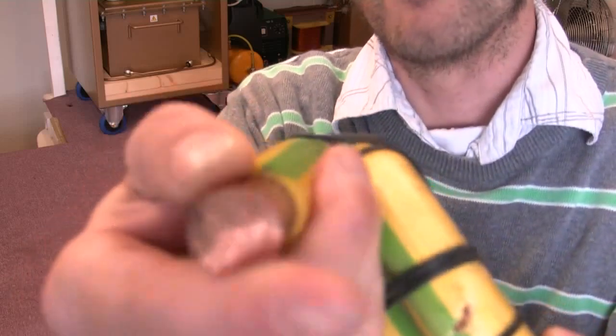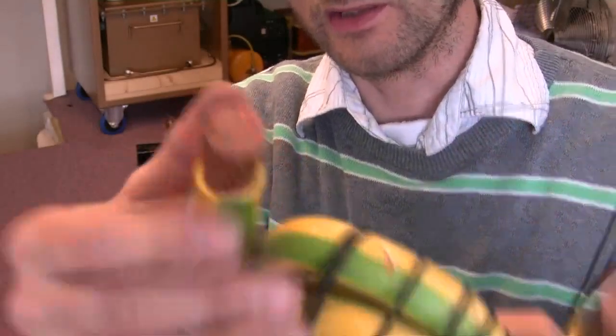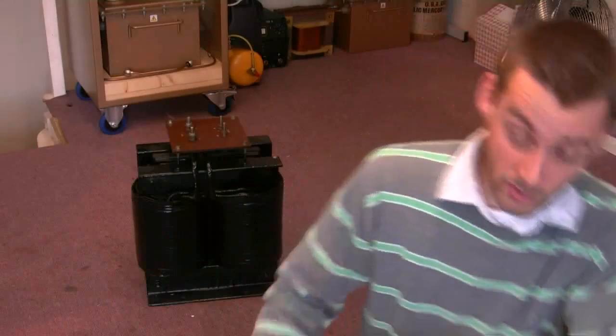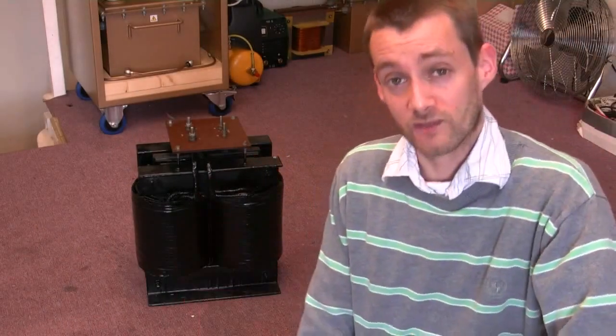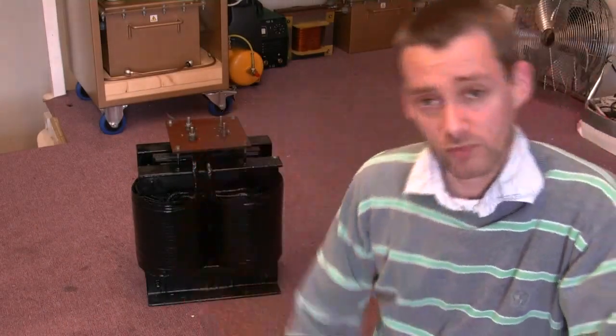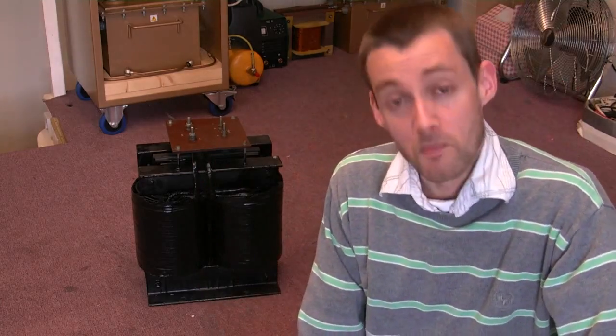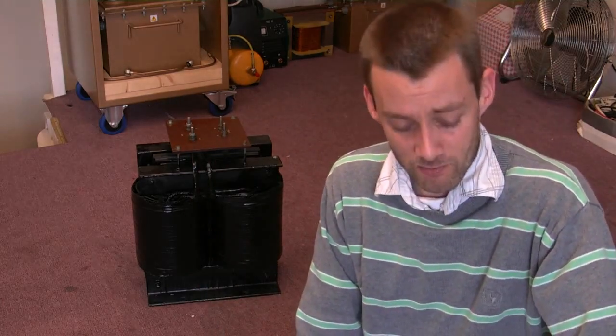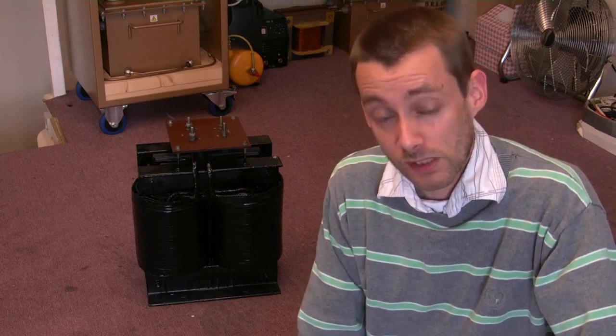I'll show you some 185, which as you can see is quite fat. On that transformer I want 275, which is a lot thicker than this. So once I get the secondaries off that transformer, I'll have quite a bit of room around the coils to put my new windings on, and from that we should easily get 10,000 amps.